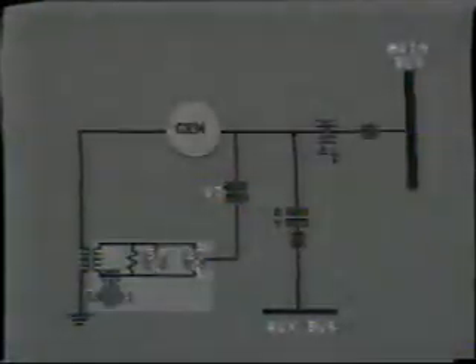But why is this necessary? We already have ground protection in the form of the 59G overvoltage relay. We also have, quite often, backup in the form of an instantaneous or time overcurrent relay in the secondary circuit. And now we have yet another. Well, the reason is that when an impedance is inserted in the generator neutral, 5 to 10% of the winding will be unprotected. If a ground fault occurs within the winding close to the neutral, the generated voltage at this point will be so low that the amount of fault current in circulation will probably be insufficient to operate the relays. The addition of the third harmonic undervoltage relay helps protect this first part of the winding.